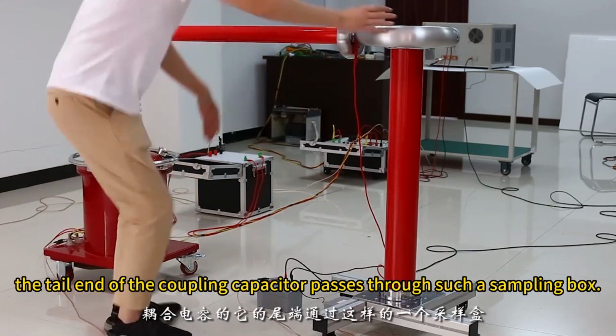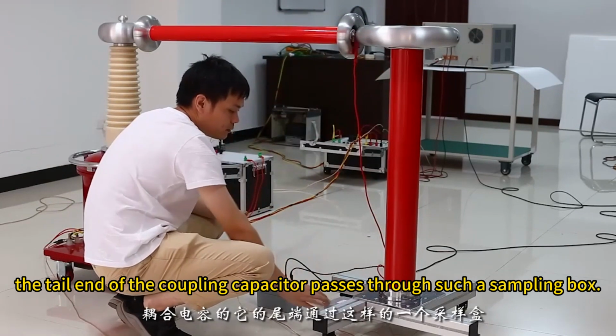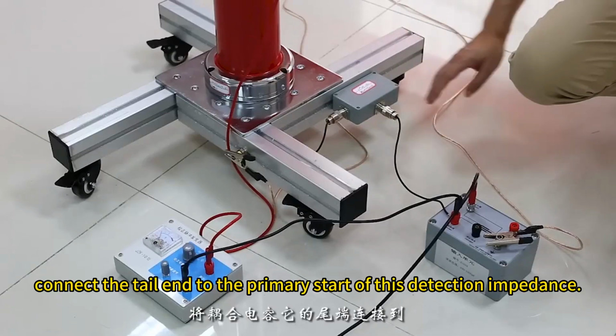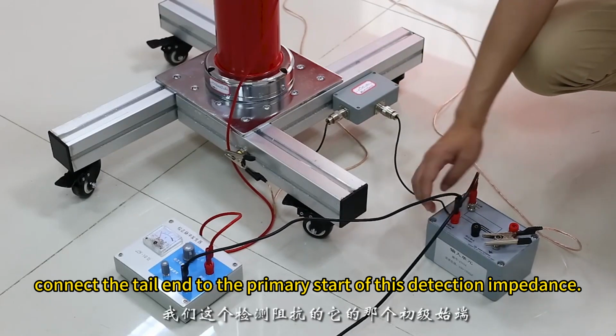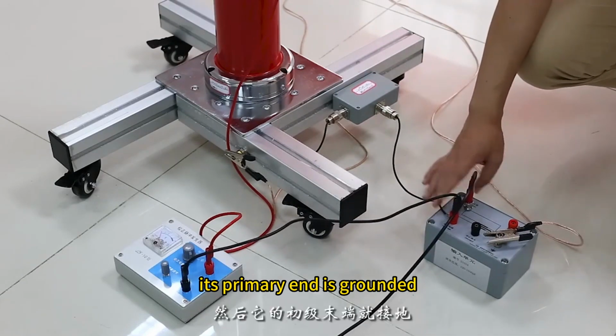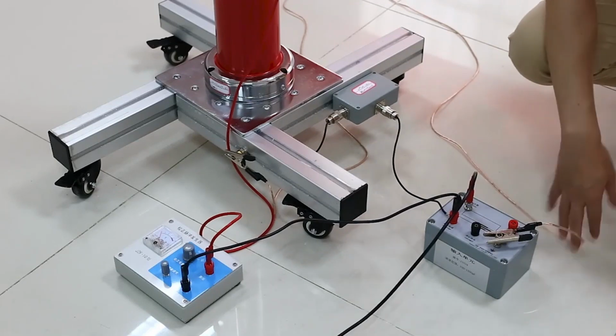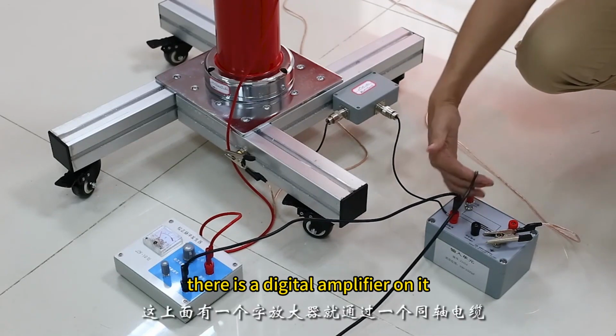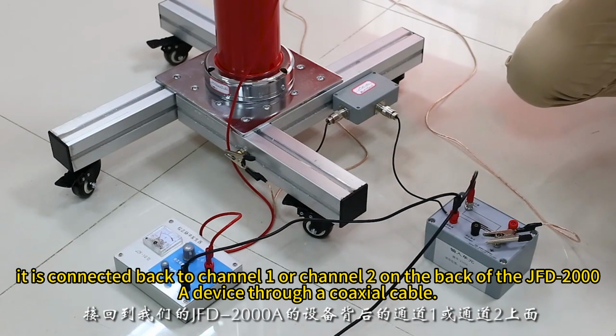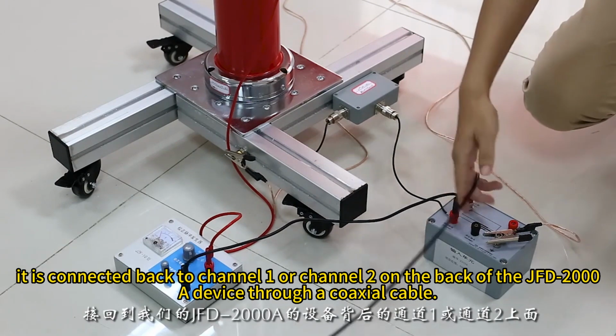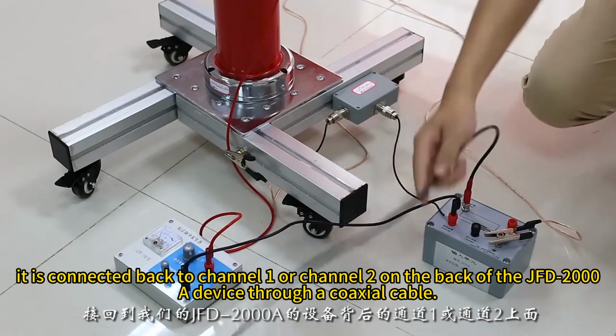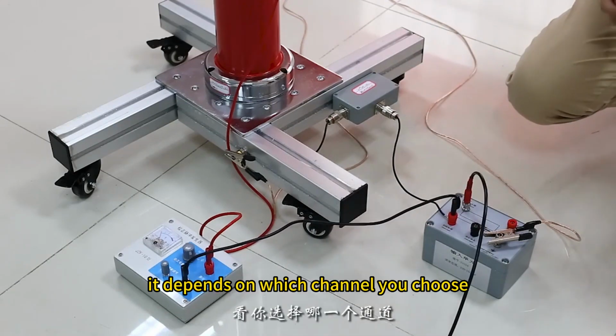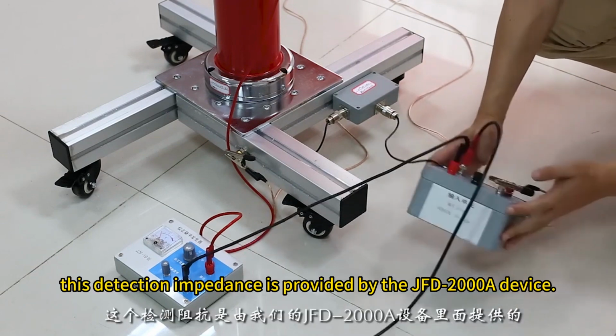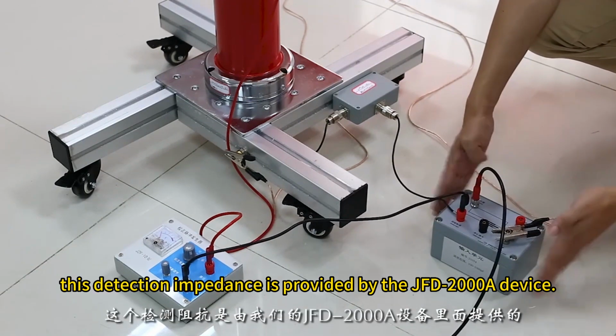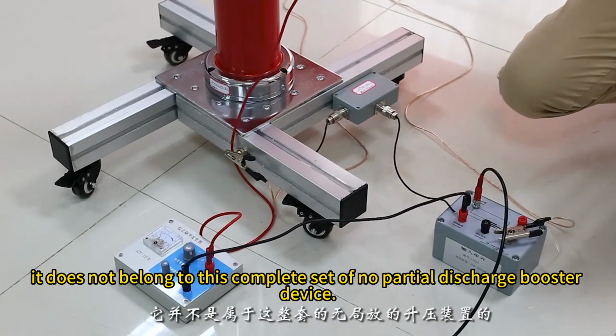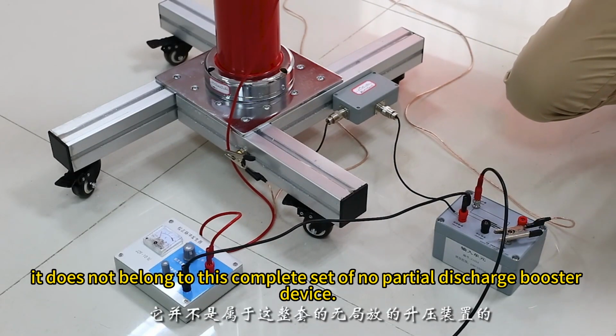The tail end of the coupling capacitor passes through such a sampling box. Connect the tail end to the primary start of this detection impedance. Its primary end is grounded. There is a digital amplifier on it. It is connected back to channel 1 or channel 2 on the back of the JFD 2000A device through a coaxial cable. It depends on which channel you choose. This detection impedance is provided by the JFD 2000A device. It does not belong to this complete set of no partial discharge booster device.